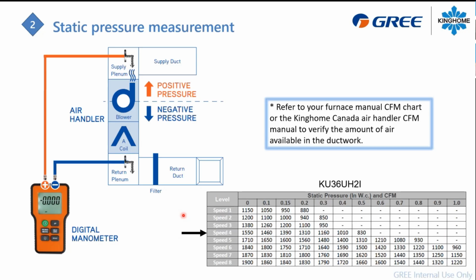Okay, if you go higher than 400 CFM per ton, sometimes you will keep water in the coil because you have too much pressure, too much air flowing through it. So maybe you will get some water damage inside. So make sure your static pressure is good regarding the chart for the CFM. This is really an important thing to do when you do your startup.